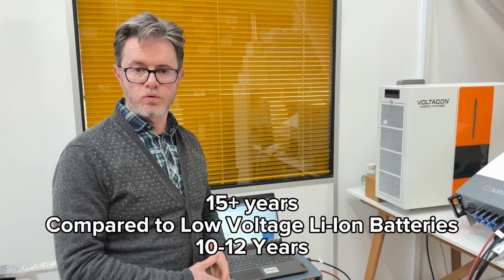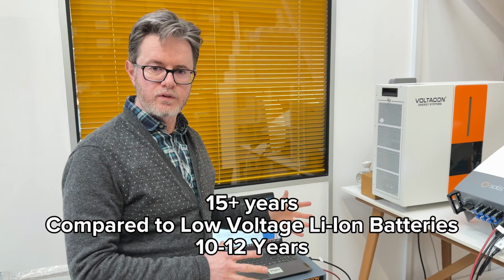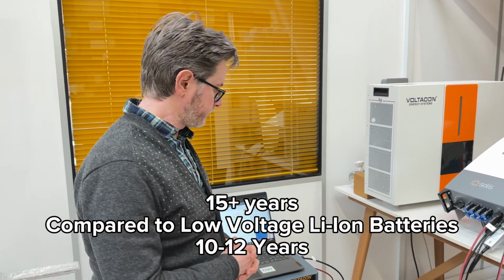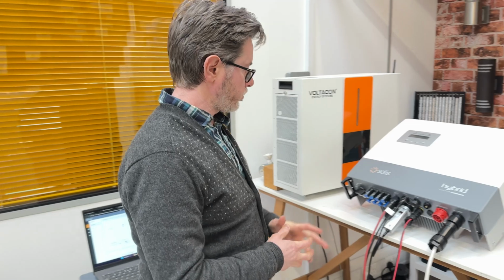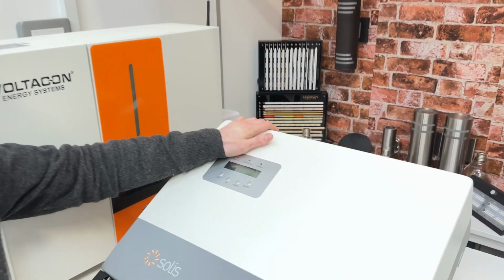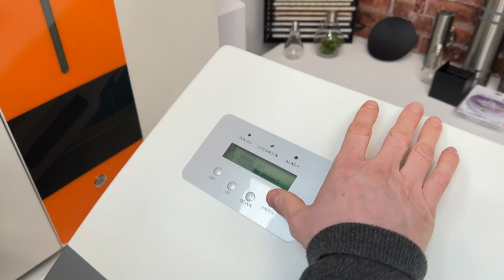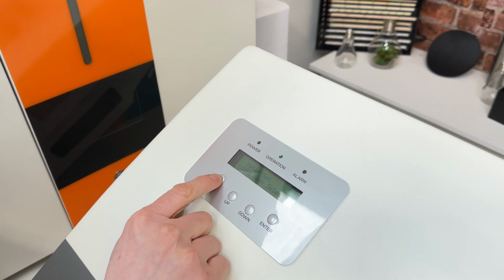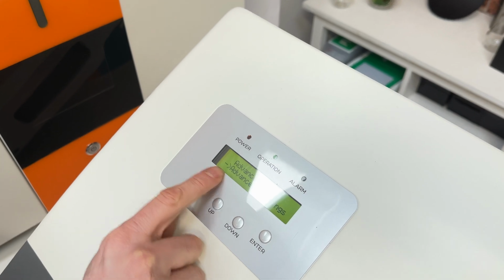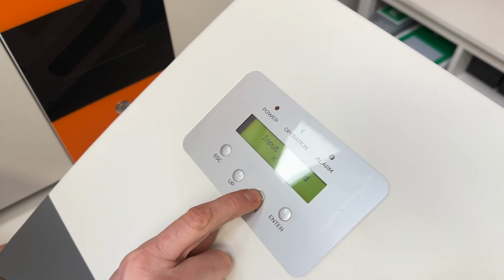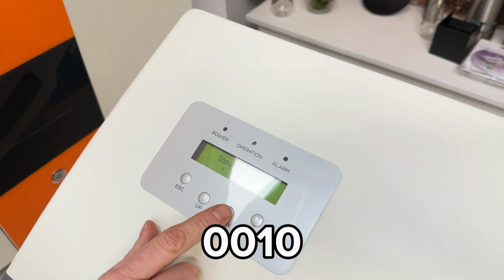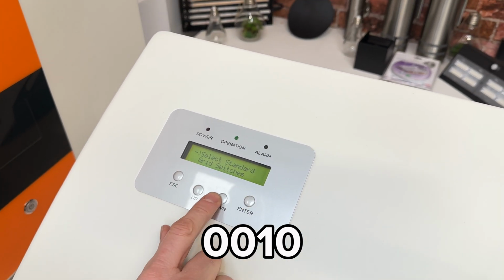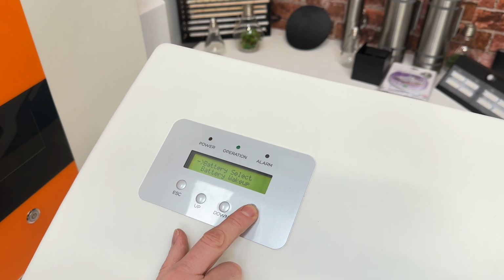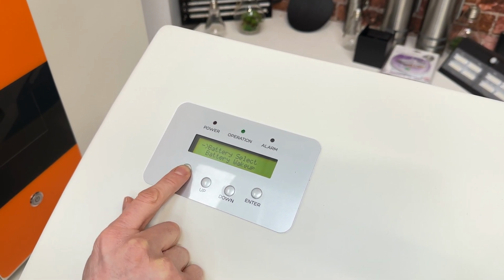Great advantages with the high voltage lithium ion batteries. They last significantly longer, 15 years or more, compared to the 10 to 12 years of the low voltage lithium ion batteries. And now I will show you very quickly how to set up the inverter in self-consumption mode. It's an easy process. You enter the menu, the advanced menu, first of all. You set the password to 0010. You select the battery control. The battery is Pylon, always.